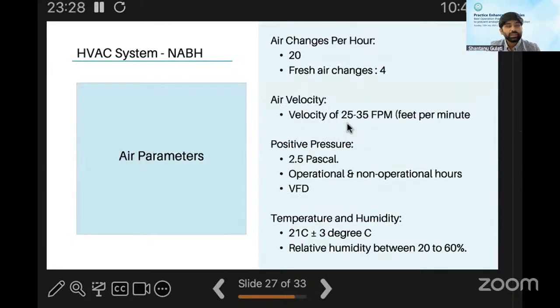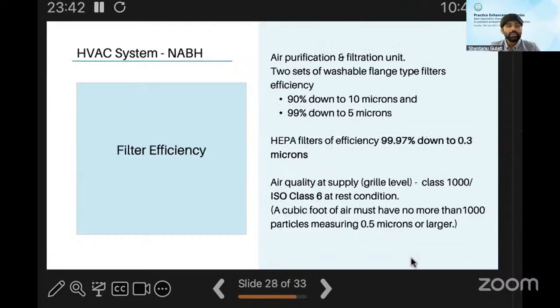So there are various air parameters such as the air changes per hour, which have to be 20 with 4 fresh changes. The positive pressure has to be about 2.5 Pascal, whether in operational or non-operational hours, and there are temperature and humidity standards. Various HEPA filters of efficiency 99.97% down to 0.3 microns have to be installed. And the air supply at the grill level, at the level of the plenum, has to be ISO class 6.